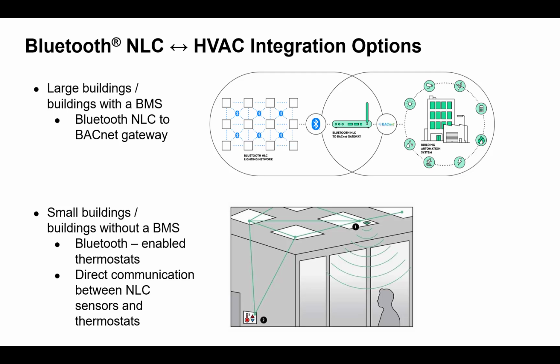I'll say a bit more about this spec on the next slide, but the idea is that you have meshed lights with the NLC concept, and every light has an occupancy sensor. So the grid of occupancy sensors is dense, giving you high granularity. Then you have the thermostat, which can simply subscribe wirelessly to this lighting information.